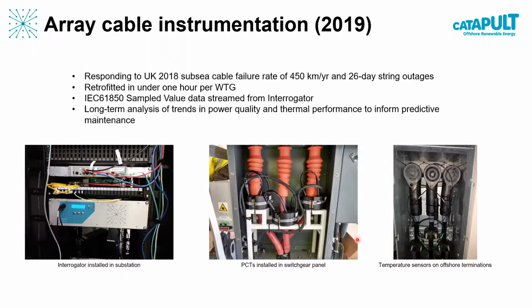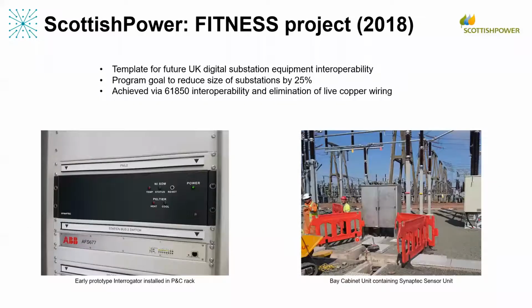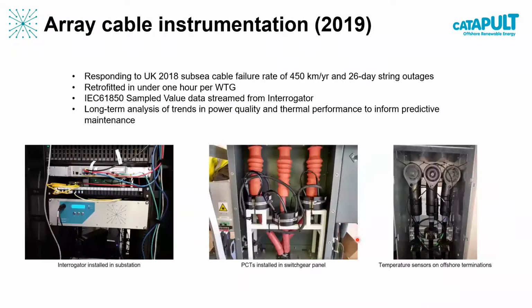Now what we're doing there is we have 3 split core CTs, and you'll see that they just look like traditional split core CTs, because they are. But the secondary of those CTs is going to a local box, which is converting those immediately and passively into optical signals. So where we're able to, we like to install around insulated cables like this, because it reduces, of course, the requirement for us to come along with costly insulators to protect the device. Because we don't have any copper secondaries, it means that we can install while the system is live. But in other situations, of course, we use traditional standoff insulators, for example, in outdoor installations. Let's see if I've got any photographs of that. I don't have any photographs of that today.